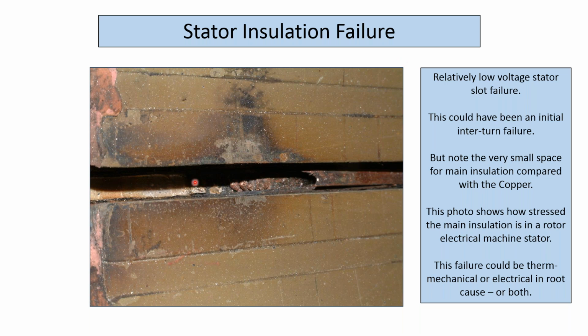Okay, this just shows a low voltage stator failure. It shows how thin the main insulation is, but for this voltage, that thickness would be ample to run for 10 to 20 years, provided there's no mechanical stress on the insulation. But if you can imagine, if this conductor moved in and out of here, or there was a force on it that put shear stress on the insulation, it would fail quite quickly.